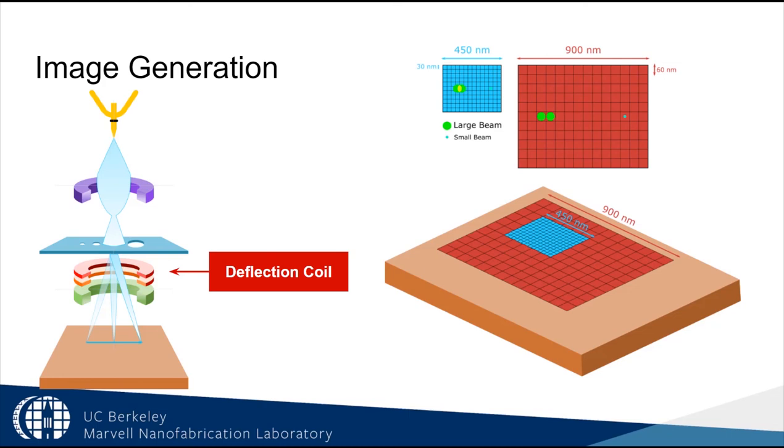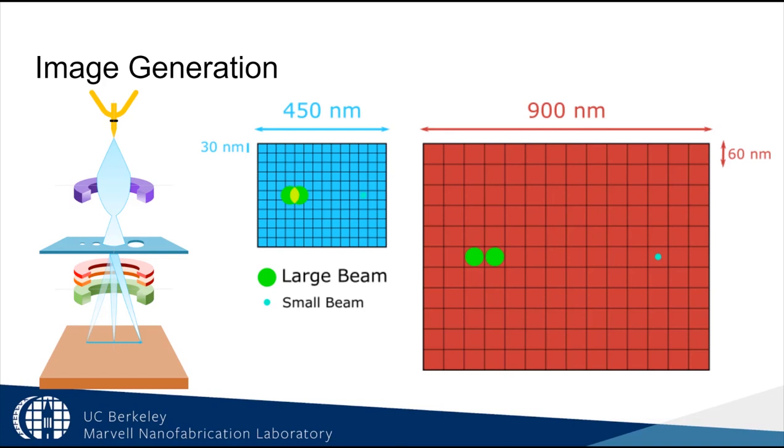In an optical microscope, you change the magnification by using a different physical lens. In an electron microscope, you zoom in simply by reducing the area over which you are deflecting the beam. This increases the magnification. If you have a very large magnification but also a very large beam, you can oversample your image where the spot size of the beam is larger than your pixel size.